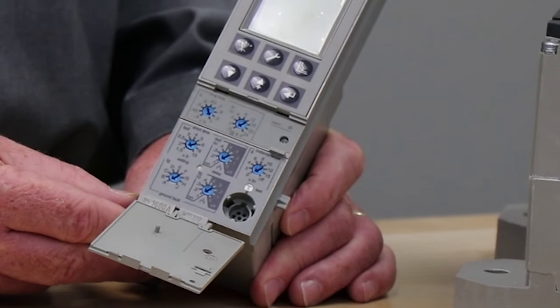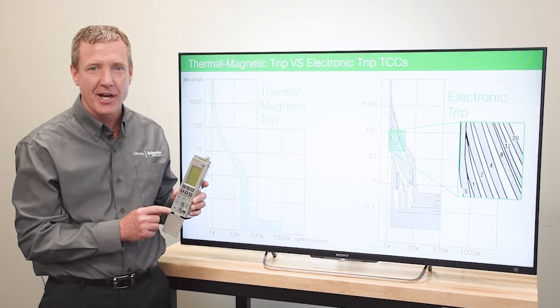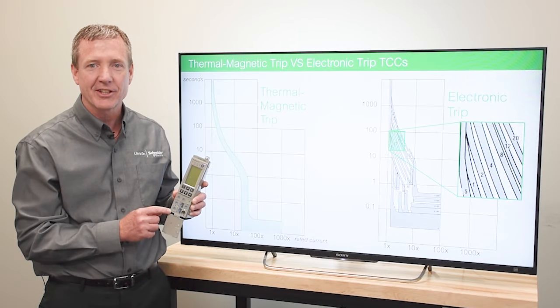As seen here, this rotary switch has nine settings. Each setting matches to a set of the distinctive time-current curves for the electronic trip unit.